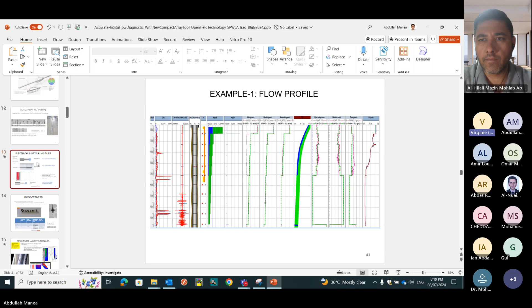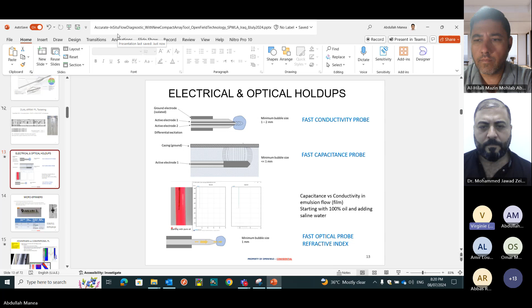The signal for optical gas on a clean probe is in the range of 32,000 raw optical counts. For oil, it can be very low, 1 or 2,000. So we have a very fine dynamic range, and at each acquisition the digital sampling is around 30 kilohertz. So we have a lot of data samples per acquisition rate, which can be 4 hertz or 8 hertz. We measure not just the gas holdup or oil holdup calculated by the firmware. We also store the raw data: minimum, maximum, average of the optical, and bubble count. So you can QC the data, but also reprocess it.